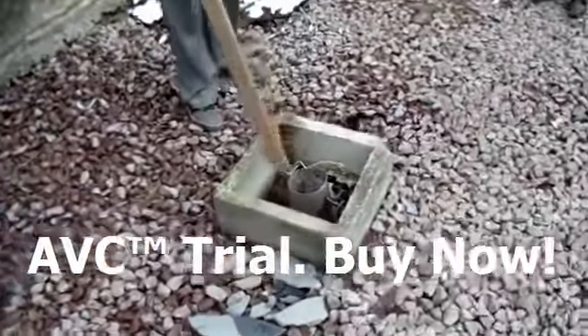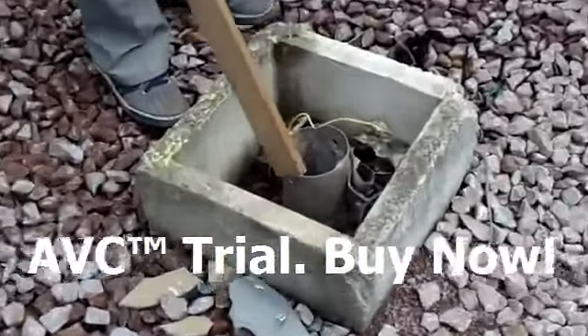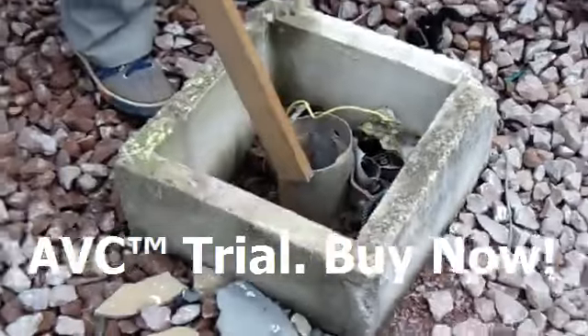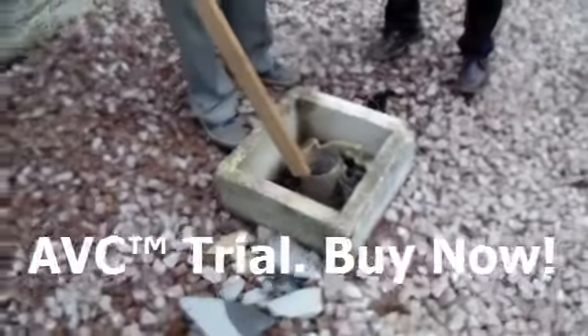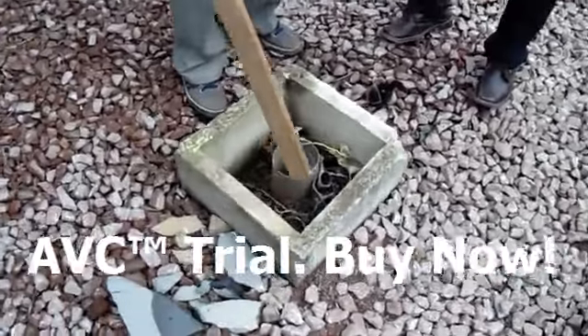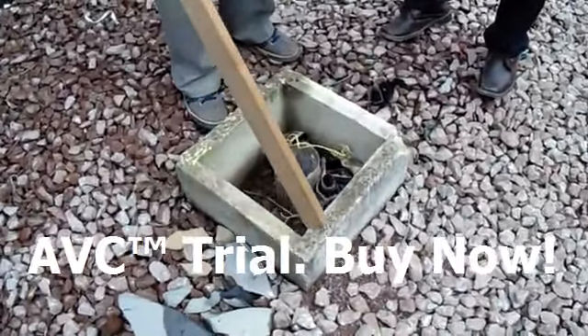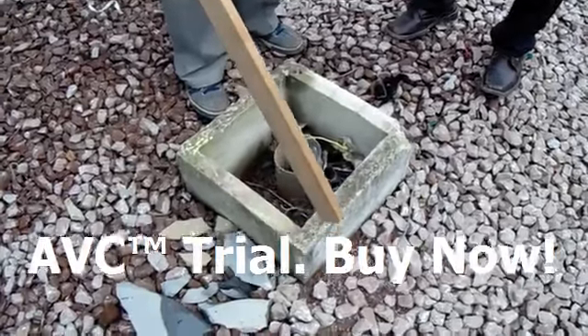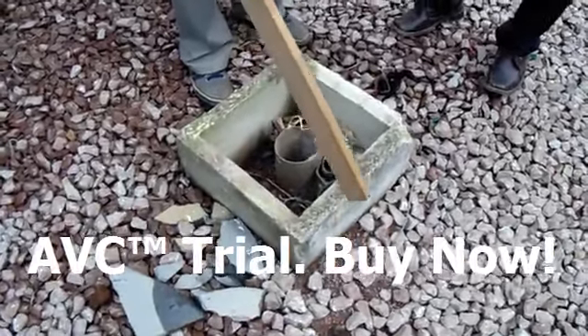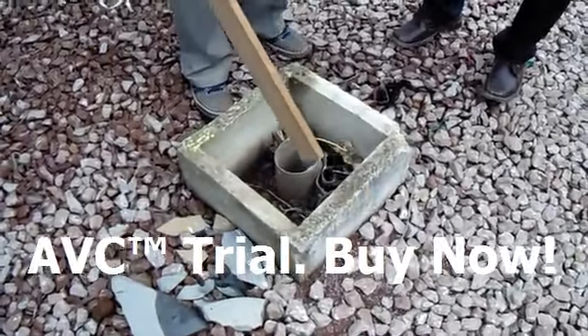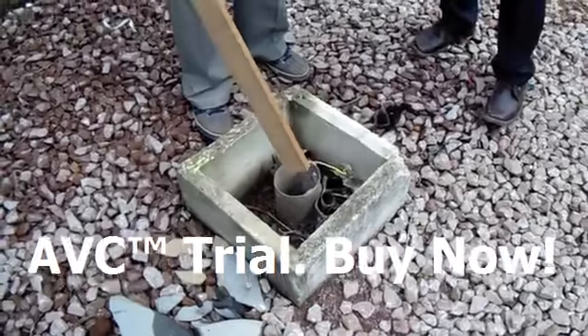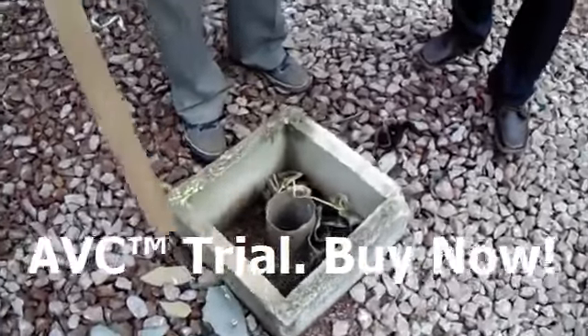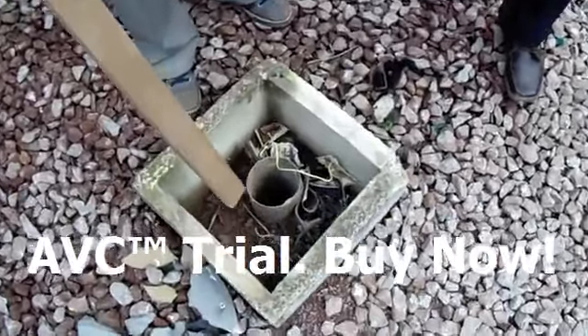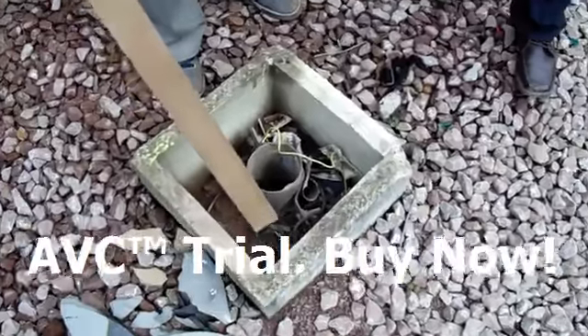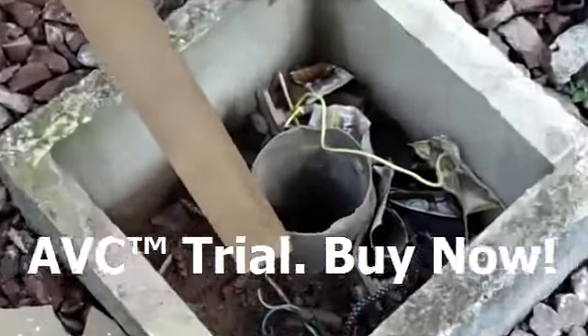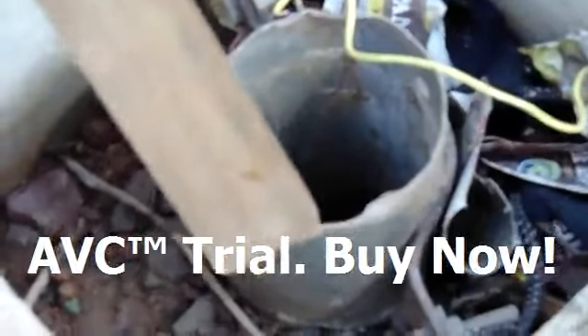This is a typical earthing, you can see it. There are 2 types of earthing, mainly pipe earthing and plate earthing. For substations we normally give the plate earthing. The plate size is 600 by 600 by 6 mm, a copper plate where the length and width are 600 mm by 600 mm and the thickness is 6 mm, and you have to make a pit whose depth is 3 meters, and then you put this copper plate in and fasten another copper strip.